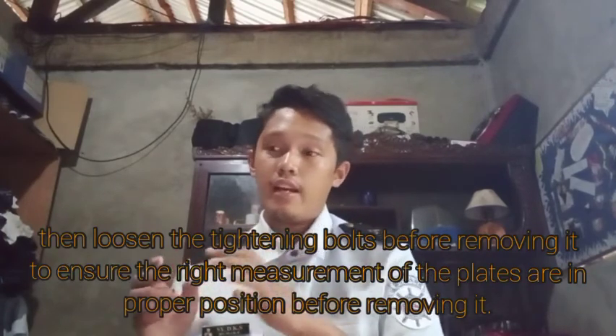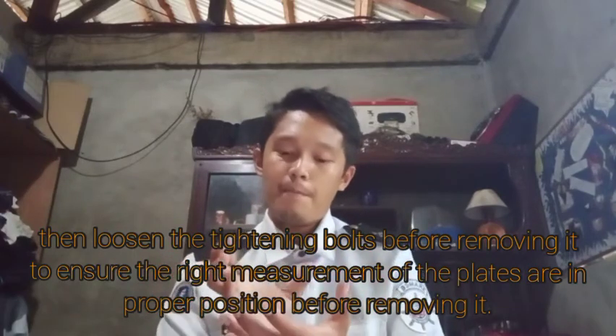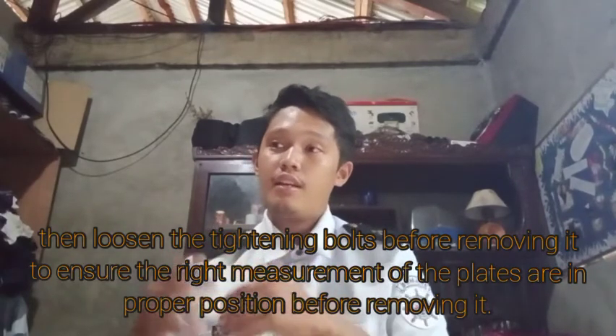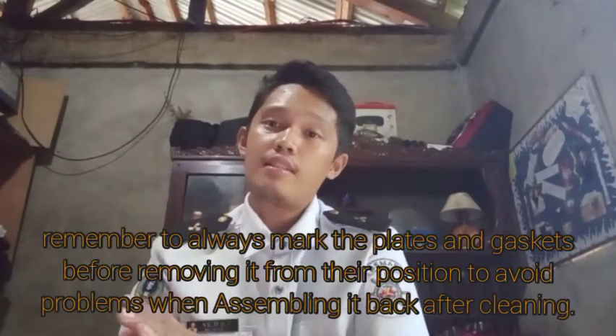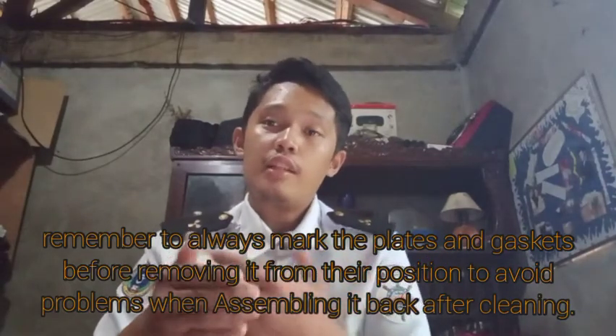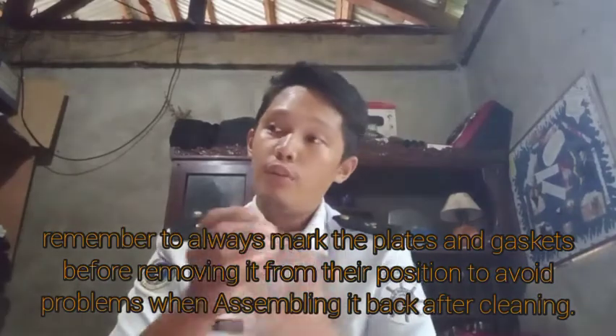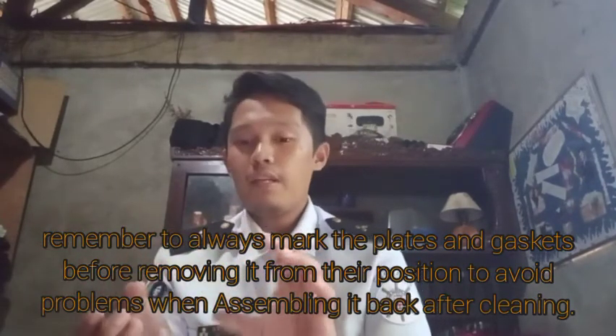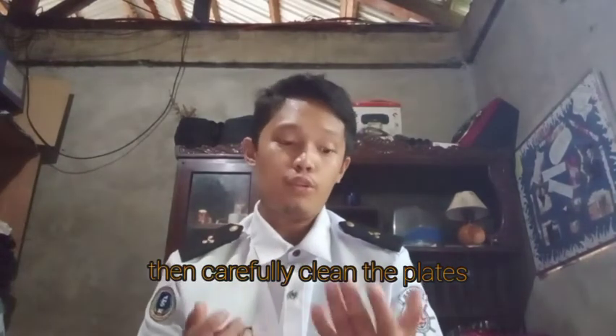Next, you should loosen the tightening bolts before removing them, because sometimes the measurement of the plates can be destroyed if the tightening bolts are not properly handled. And if you want to remove the plates and remove the gasket, you should mark them so that, if you return them, you know the right place for each. After removing the plates, you can now easily clean them. But you should always clean the plates carefully because they are sharp. You should always use gloves.